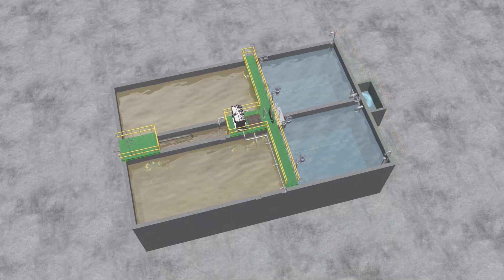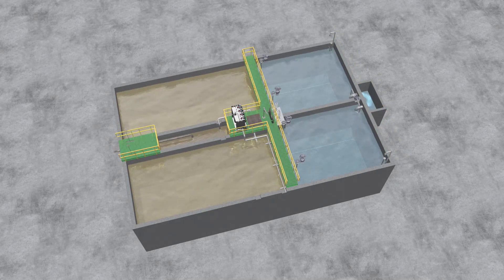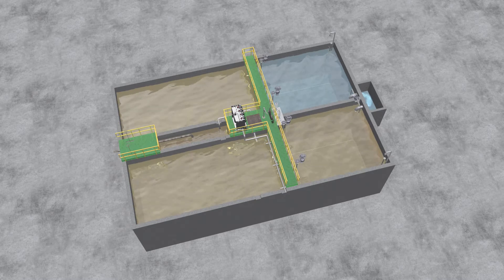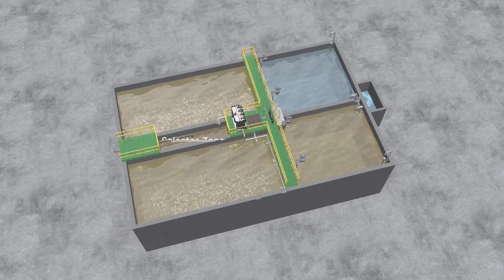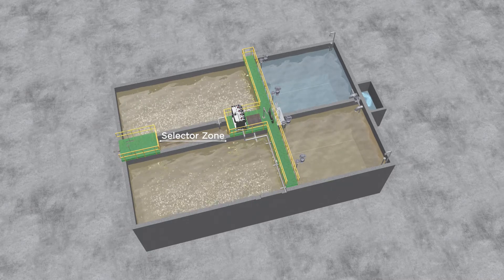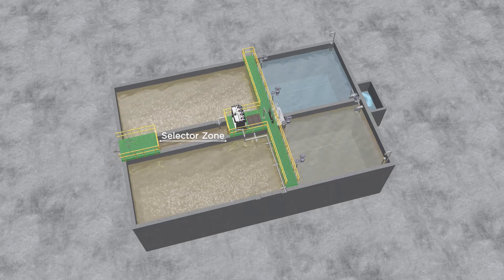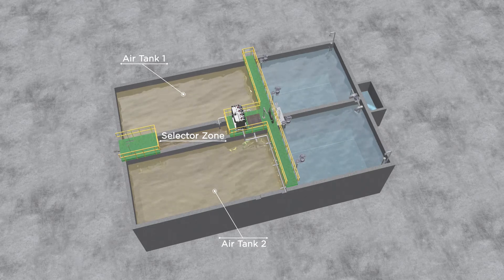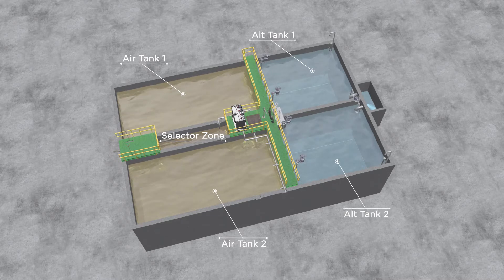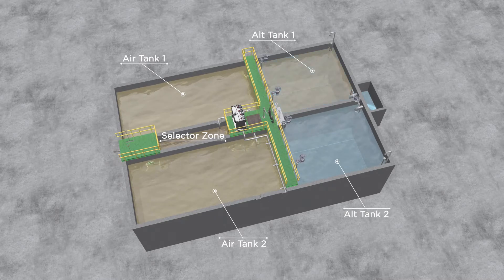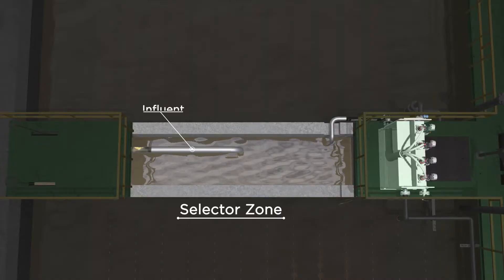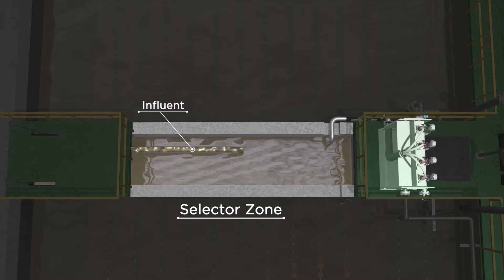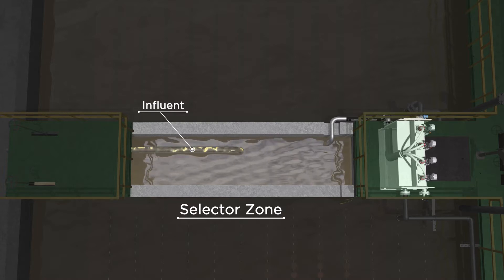BioCoast is a hybrid process that combines both continuous and cyclic activated sludge processes, featuring a constant water level and continuous influent and effluent flows. The system includes an anaerobic selector zone for biological phosphorus removal, included as part of the aeration tank volume. The aeration tank, or air tank, is hydraulically connected to two alternating sludge recycling and settling tanks: Alt Tank 1 and Alt Tank 2. The influent wastewater flow travels from preliminary treatment into the selector zone, which is designed as an anaerobic volume to provide enhanced biological phosphorus removal.